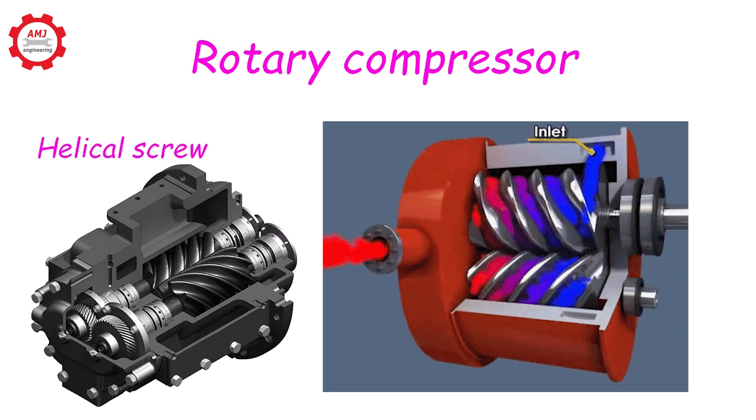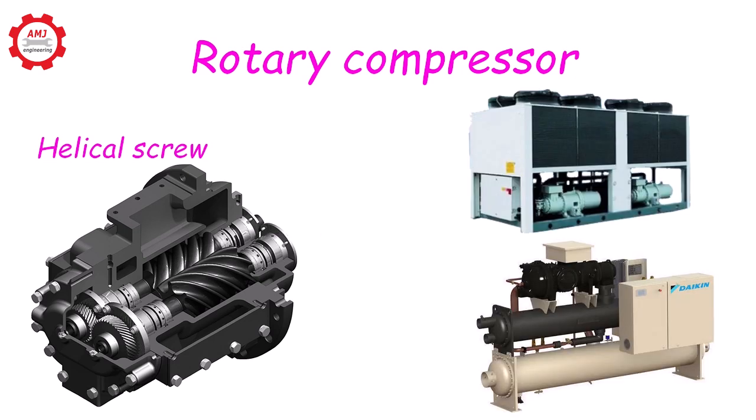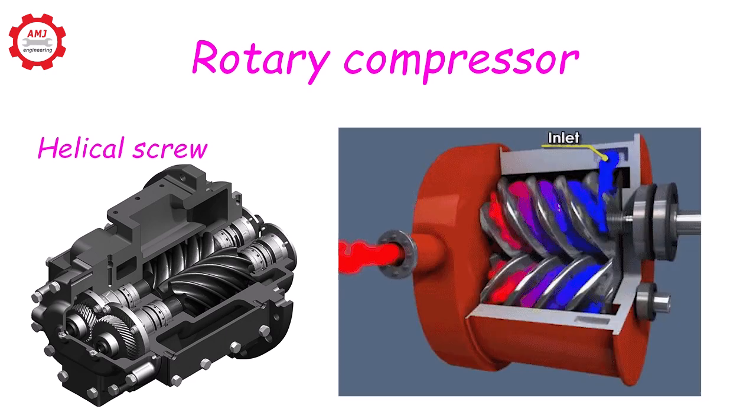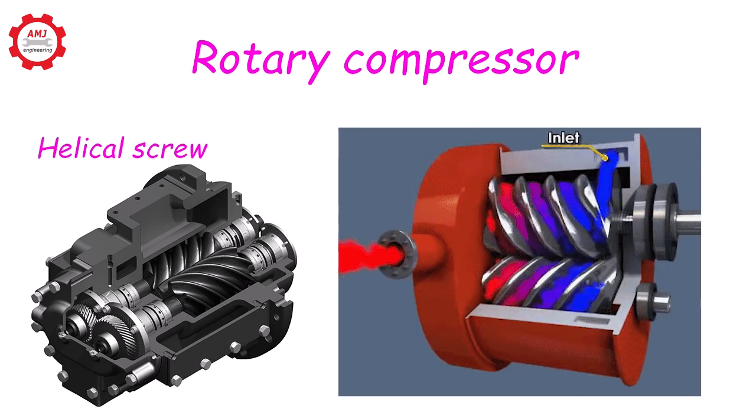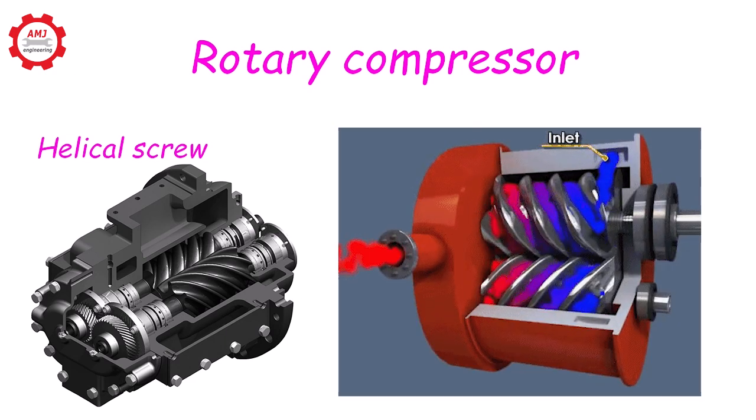The helical screw is the more common type; they are used on both air and water-cooled chillers. These chillers are typically available in 70 to 400 tons of refrigeration. Screw compressors work by using two interlocking rotating helical rotors to compress the refrigerant.